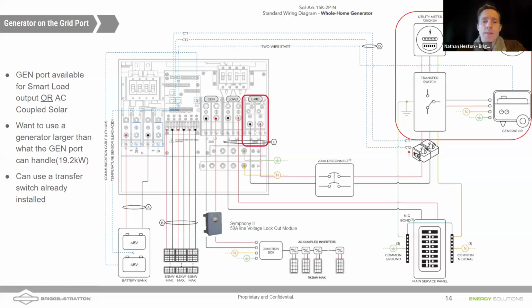That will basically, anytime that generator is running, shut off that AC coupled solar. If you don't have this, there are other relays you can get, and Daniel and I can provide a recommendation. The PSP product Daniel is showing on the screen is programmable. You can program it to turn off anytime that generator has started. It comes in 60, 100 amp, and there's even a 200 amp version. That product's a couple hundred dollars, a little more expensive than our line voltage module.